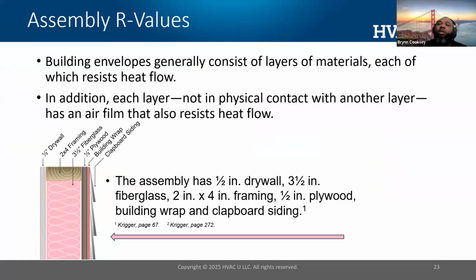Another thing to consider is, is the building properly insulated? In the older housing stock in my neck of the woods, Metro Detroit, we have houses from the 20s, and they don't have any insulation inside their walls, very little in their attic, if any. So as a result, this is going to change the demand or requirement for the size of heat pump that needs to go there. So if you're running a program for heat pump adoption, you really need to make sure that your contractors or trade allies are performing load calculations. It's critical. If that load calculation isn't done, which accounts for the leakiness of the building shell and whether the shell has insulation or not, you are going to set yourself up for bad outcomes.